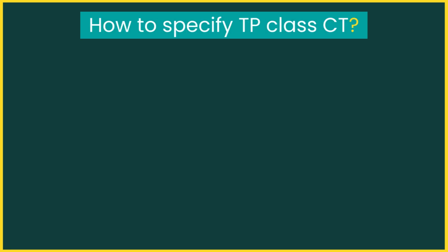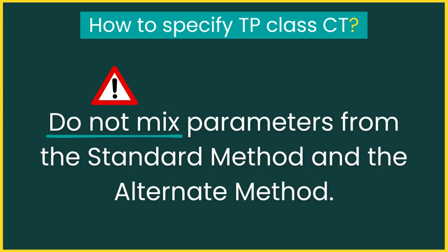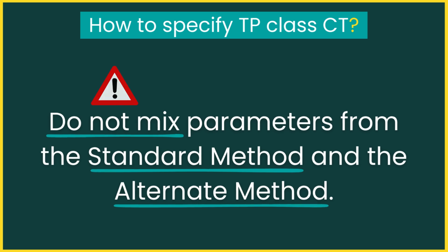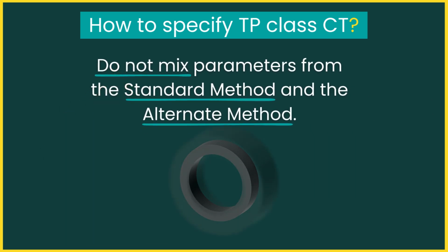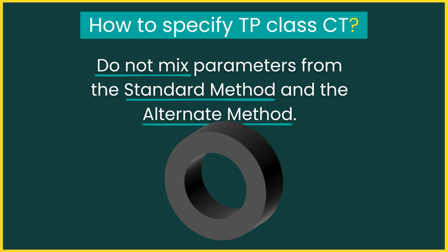A very important note here: do not mix parameters from the standard method and the alternate method. If you do, the CT will likely become oversized and uneconomical. Correct specification requires choosing one method and sticking to it.